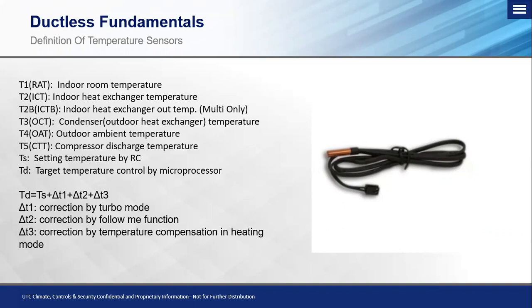And then finally, our Delta T3, which is a correction by temperature compensation in heating mode. So what this is, you can essentially put an offset on the return air thermistor, depending on if you're overheating or if you're underheating a space, and follow me just hasn't been a reliable option to resolve that. Okay, now essentially what it's doing is it's telling the T1 sensor, hey, I'm reading 75, and you program a custom offset on there to read 4 degrees less than what the actual reading of that temperature sensor is. So if it's reading 75 and you put a negative 4 degree offset on there, that system is going to read 71 at that return air sensor. And the reason that we do this is, of course, if you have an overheating situation, we're essentially fine tuning that sensor to meet the needs of the customer to make sure that they're satisfied.